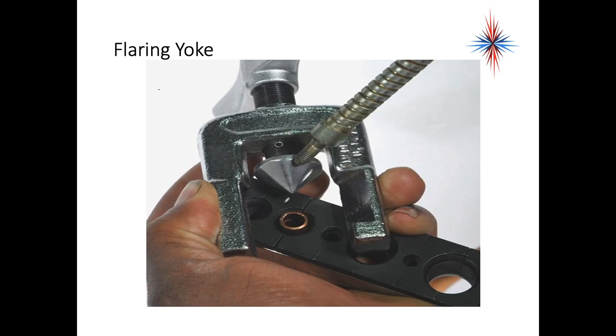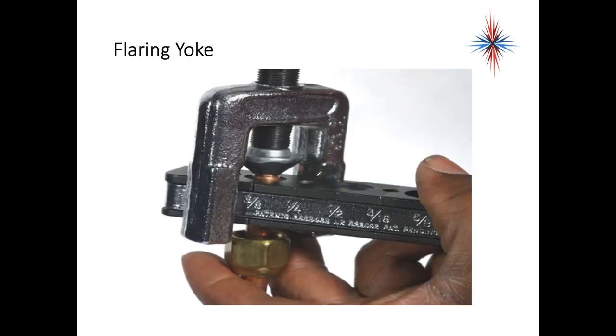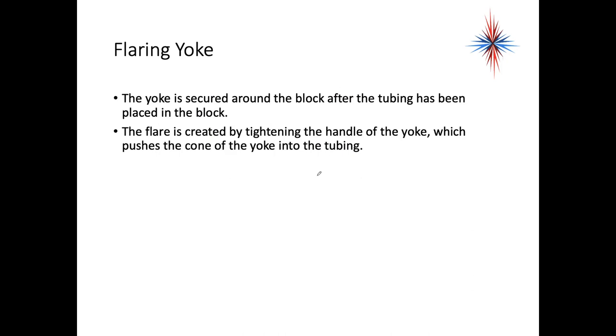You put the flare yoke on, you twist it slightly to lock it in place, and that triangle has to be exactly centered into the tip of that pipe. Don't start putting pressure on that before it's exactly centered. The yoke is secured around the block after the tubing has been placed in the block.